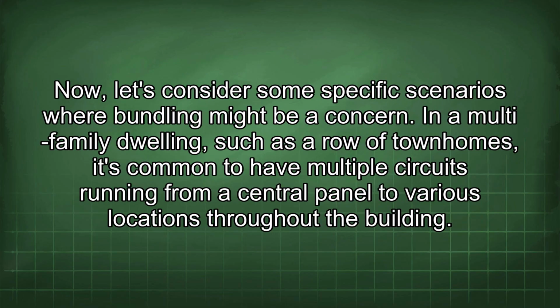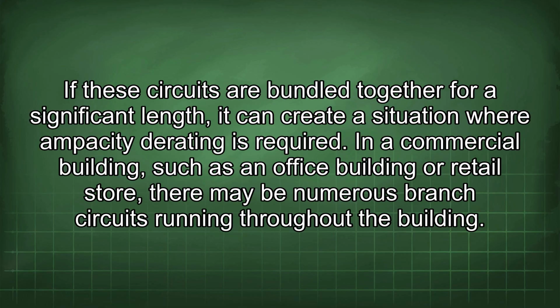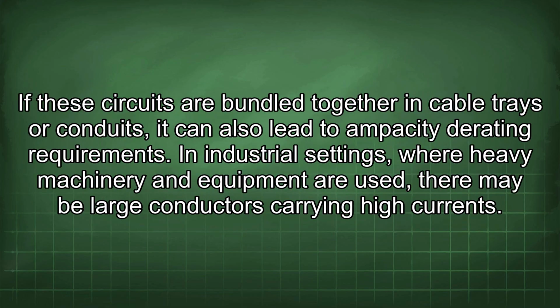Now, let's consider some specific scenarios where bundling might be a concern. In a multi-family dwelling, such as a row of townhomes, it's common to have multiple circuits running from a central panel to various locations throughout the building. If these circuits are bundled together for a significant length, it can create a situation where ampacity derating is required. In a commercial building, such as an office building or retail store, there may be numerous branch circuits running throughout the building. If these circuits are bundled together in cable trays or conduits, it can also lead to ampacity derating requirements.